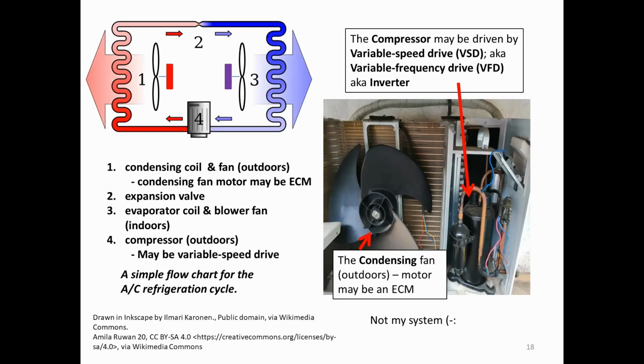So in the diagram above, you can see that you have a condensing coil and a fan, both of which are outdoors. The condensing fan motor may be an ECM, or it may not. You have an expansion valve, which doesn't concern us. The blower in the furnace is 3, and it's blowing over a coil of compressed cold fluid and evaporating it, which is why you get cold air indoors. And the compressor may be a variable speed drive, which is outdoors. And the compressor, if it is a variable speed drive, may also be a source of RFI.